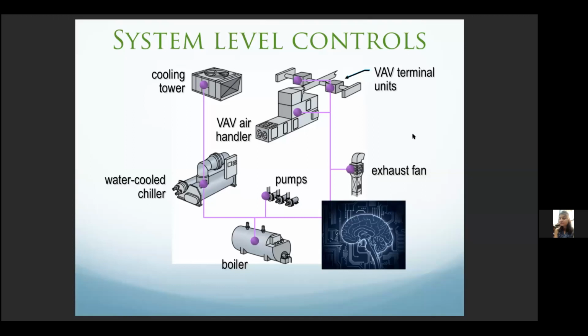There is also programming at the unit level controls, so in case they lose connection to the system level controls, they can operate on their own. But the system level control may decide to change the set point based on outdoor air temperature, for example, or may implement a reset strategy, etc. We'll dig into that more as the slides progress.